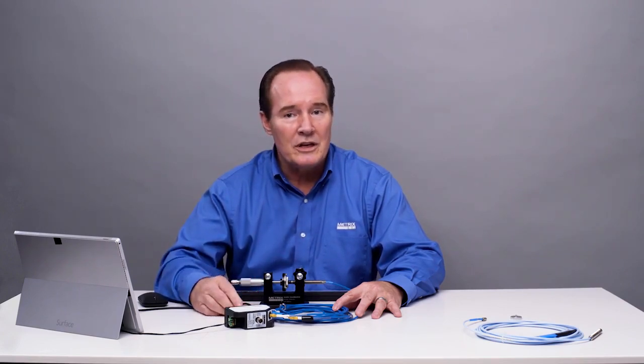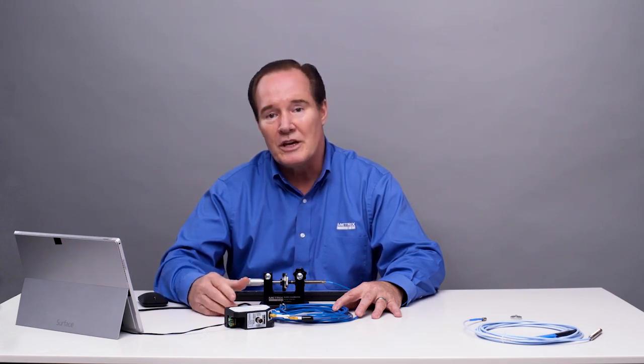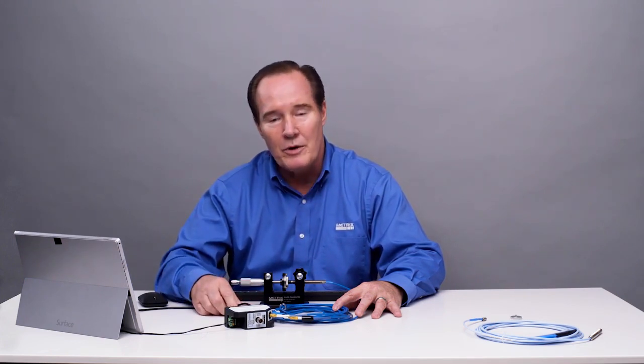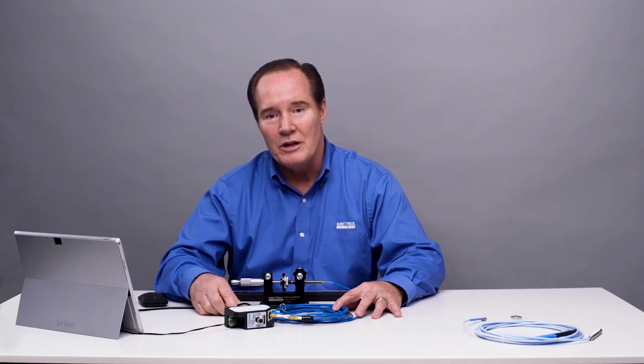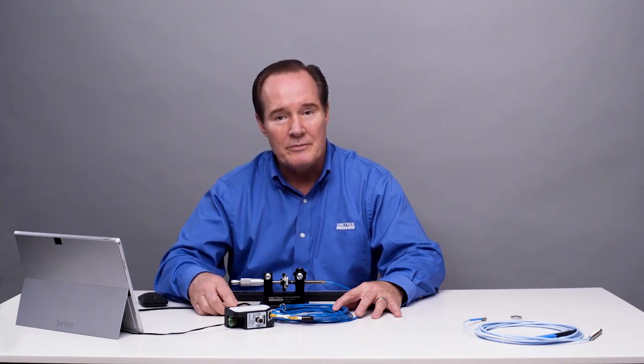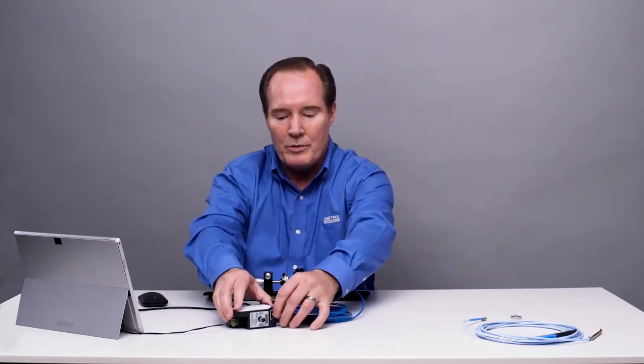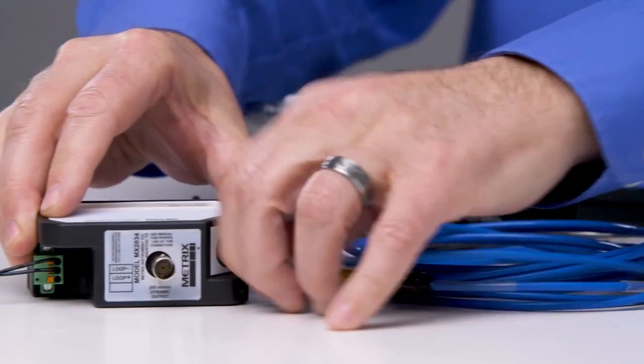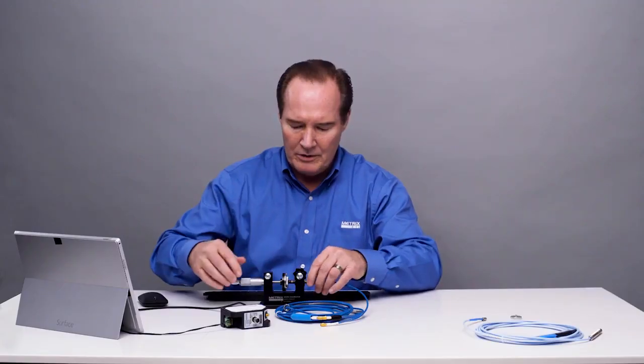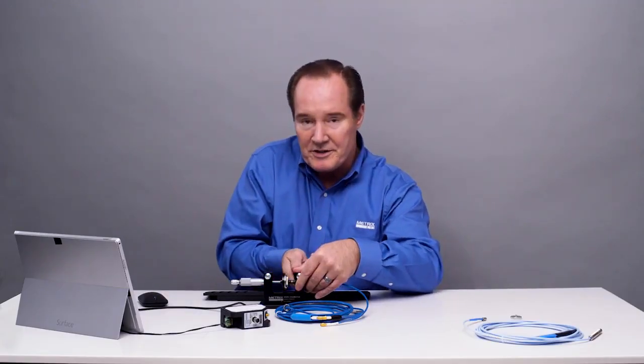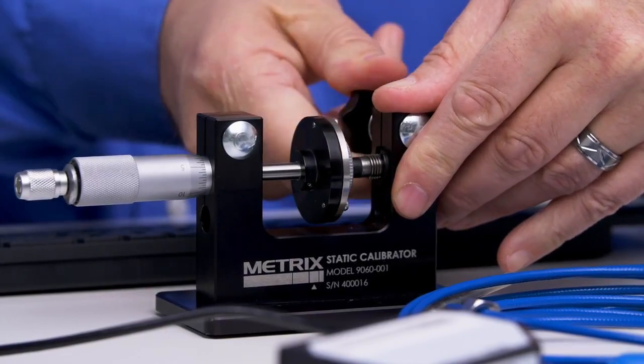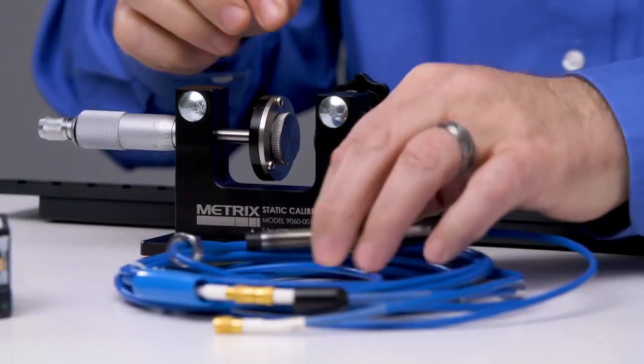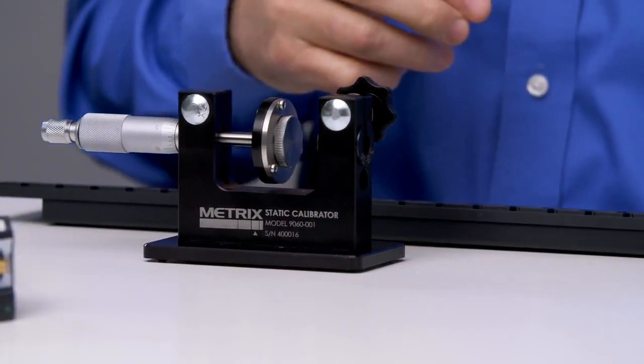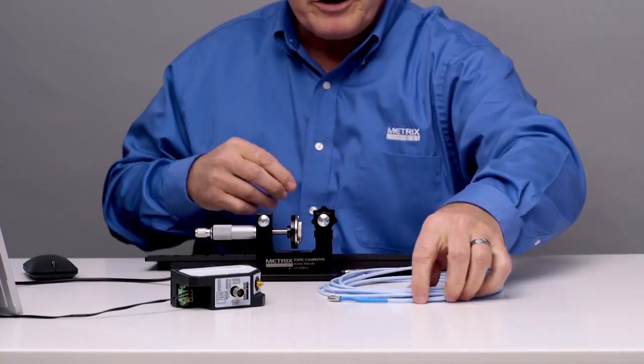Let's see if it works with the competitor's probe and cable and see if we can get a nice linear characteristic, well within the 190 to 210 millivolts per mil required from API. So let's go ahead and do that demonstration. I'm going to go ahead and change out the probe and cable. So I'm going to take the cable off the digital proximity system, and then I'll go ahead and remove the probe from the static calibrator. Then I'll go ahead and put in the competitor's equipment.